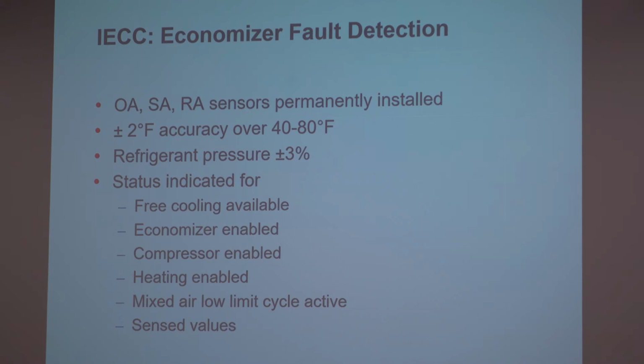We want to indicate status. If you go up to the unit and you notice that it tells you some way, either through blinking lights or through real language, words, essentially. If it tells you in words that something's broken, you're able to call for service to have them go out and fix it. A lot of these are on the BACnet interface. You can actually have them dialed up and maybe fix things from your internet connection, or you might have to roll a truck out to replace a sensor. So the status that we have to have as a minimum is whether or not it's available, whether or not it's enabled, and then if there's other limit cycles that are active or not, and what those values are.